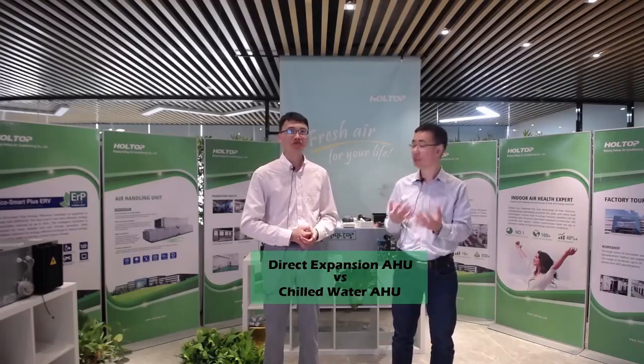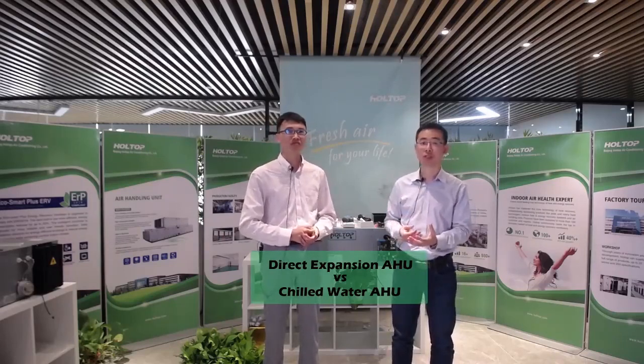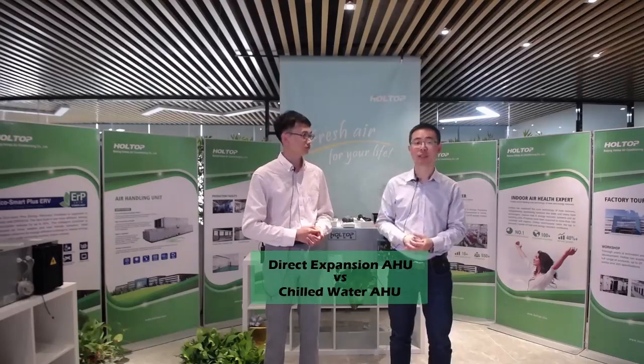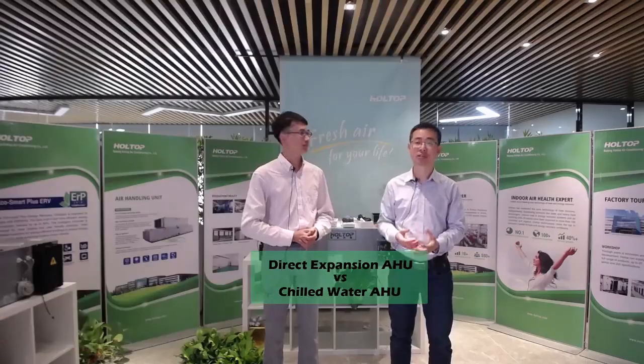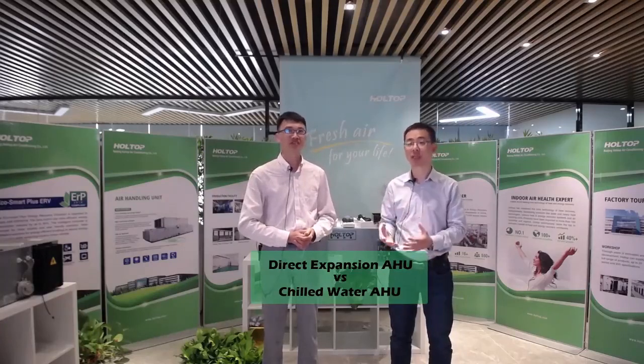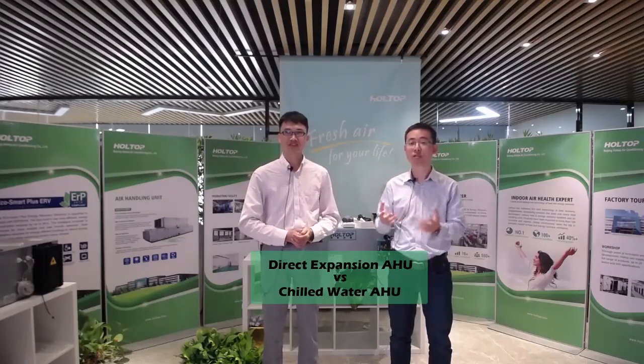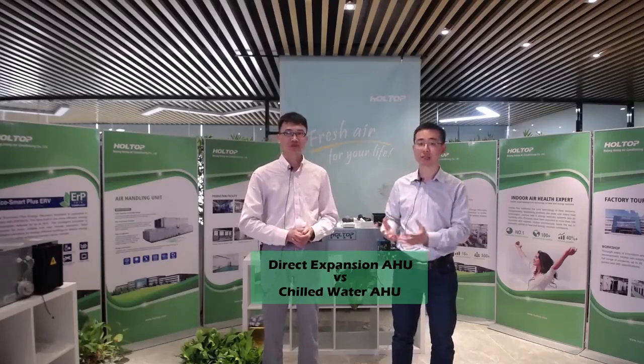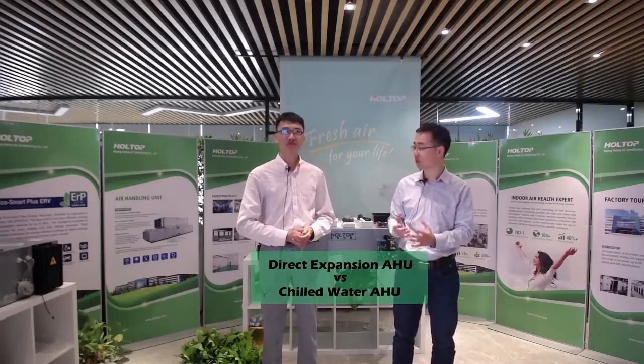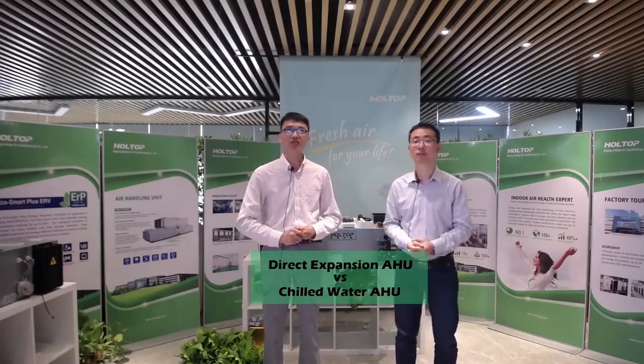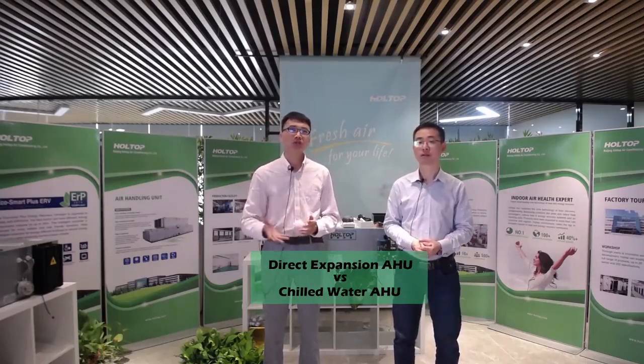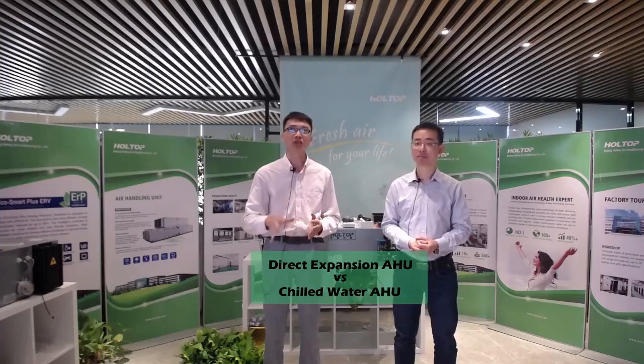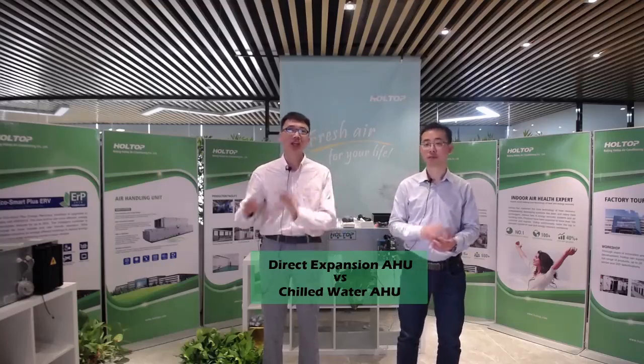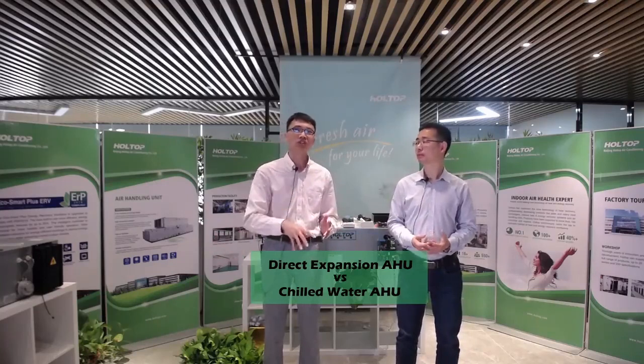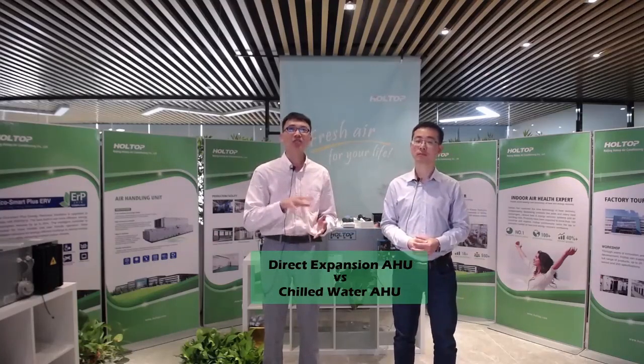So what is the advantage of the DX system AHU over the chilled water AHU? Here we'd like to have a very quick review. The direct expansion and chilled water central AC systems are both used in different places depending on the application and the size of the place to be air conditioned. Both of them have their own advantages and disadvantages. Let's see the comparison. In the direct expansion type of central air conditioning plants, the air used for cooling the room is directly cooled by the refrigerant in the cooling coil of the air handling unit. This heat transfer process is more efficient, directly from the refrigerant to air, since there is no secondary medium involved in the heat transfer, resulting in higher cooling efficiency.